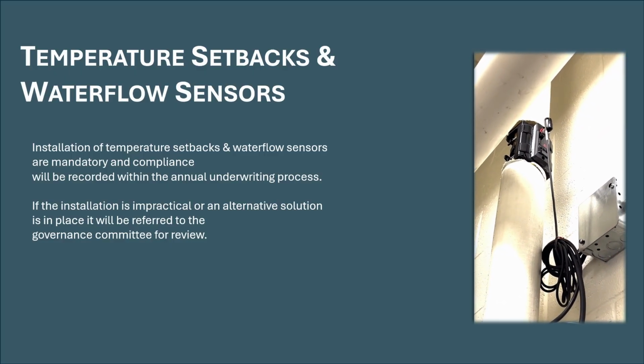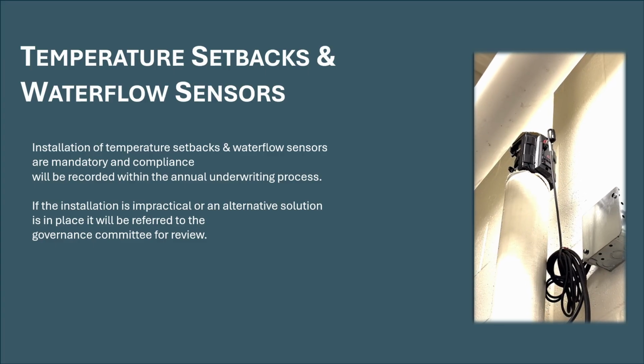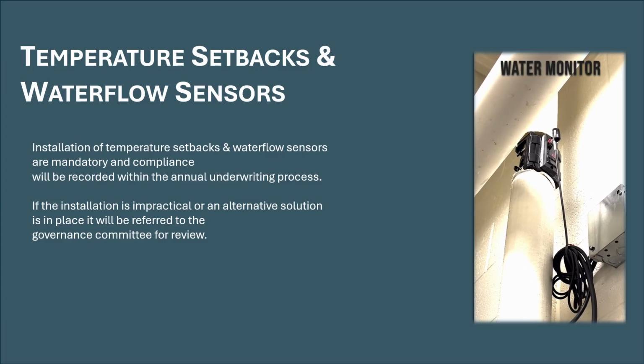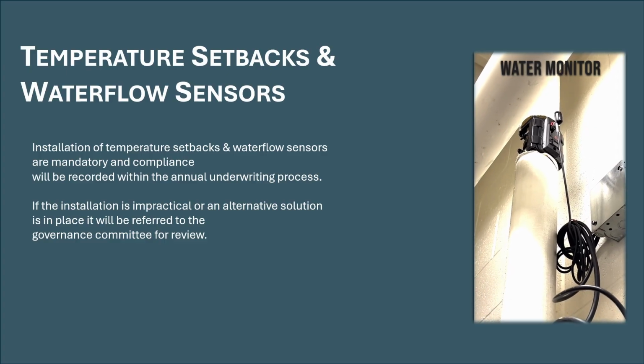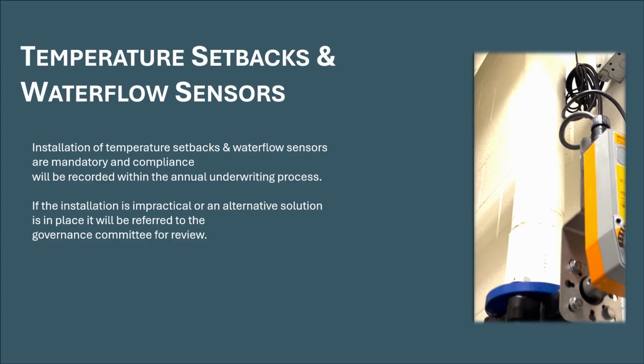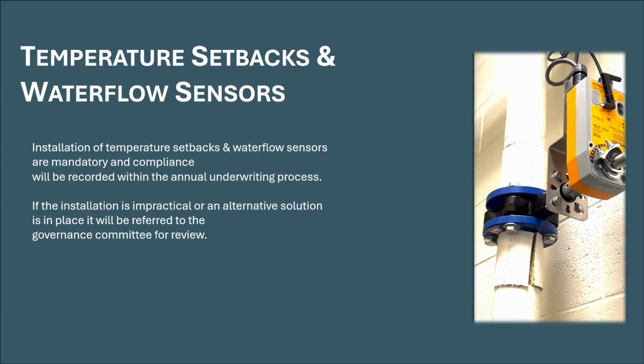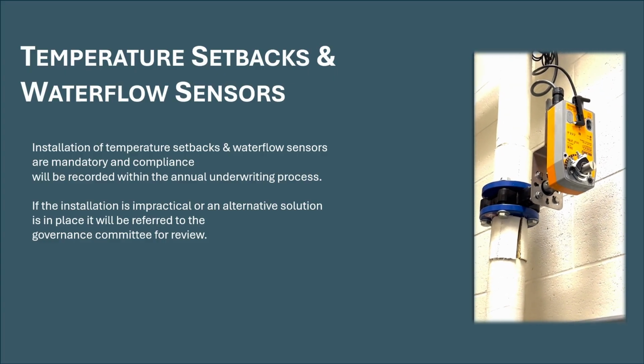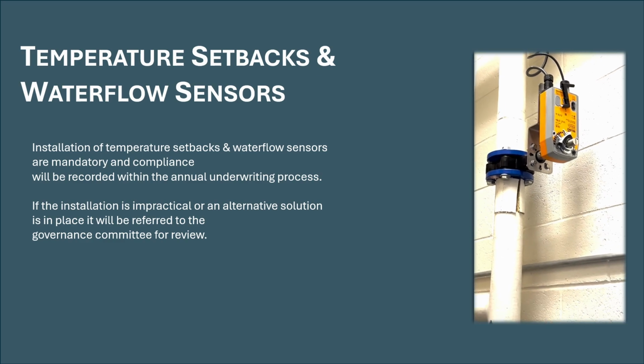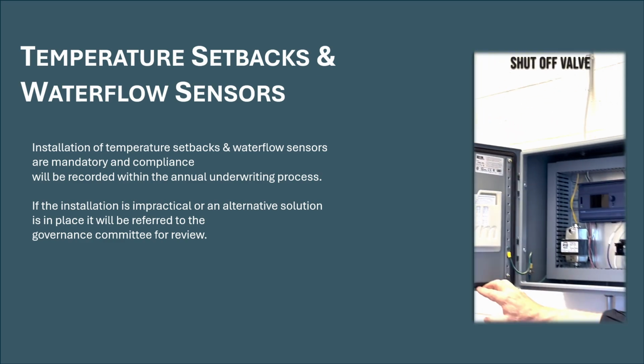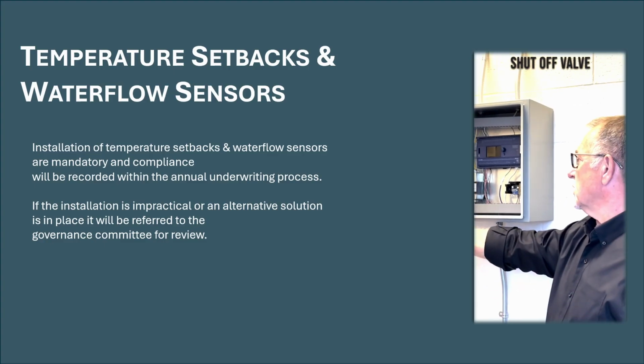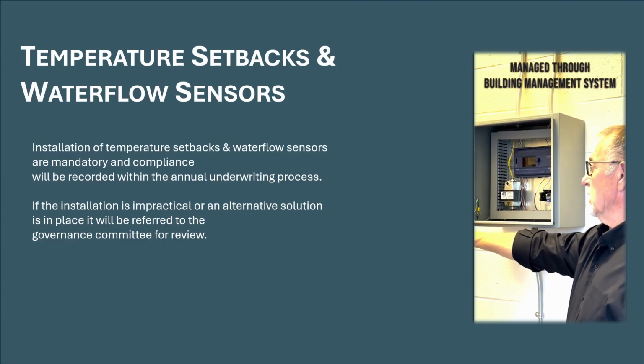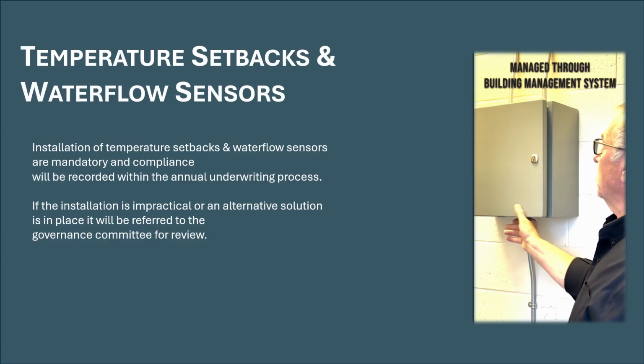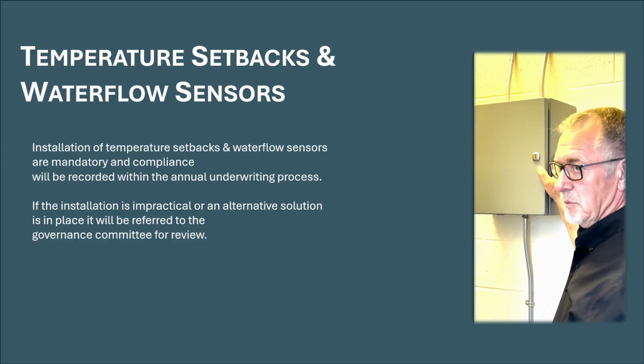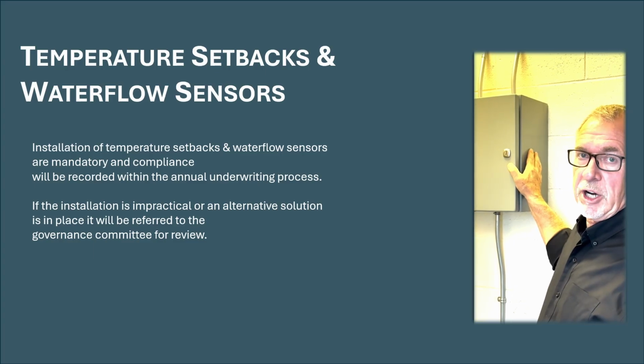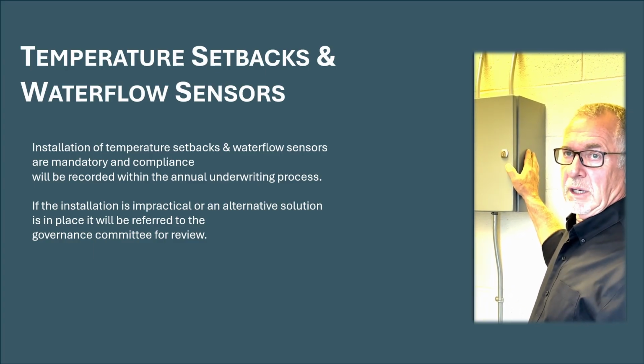The device that we're looking at right now is the water monitor. And when it sees an anomaly, as I said before, it will trigger off this shut-off valve, the orange valve that we're looking at right now. That valve will automatically shut off. And then that is managed through what we call our building management system, our BMS system, which is tied into all of our buildings. Every one of our sites has this. It's a really good device. Costs about $25,000 per site. It's covered by the Alberta government through the IMR grant, and it's worth its weight in gold.